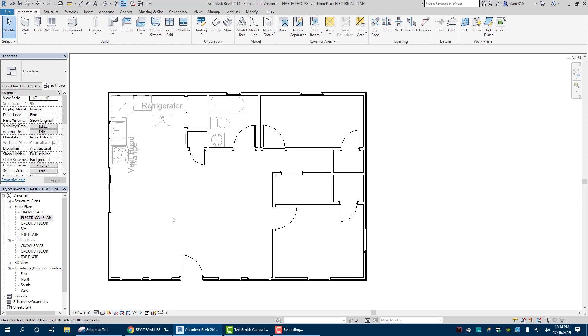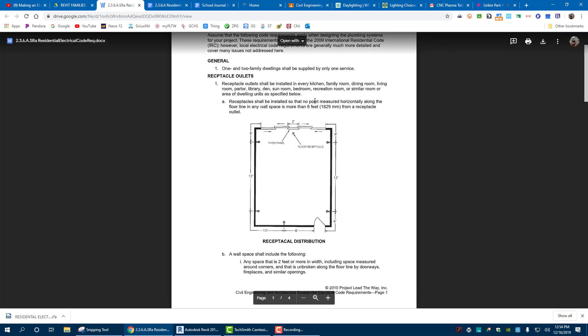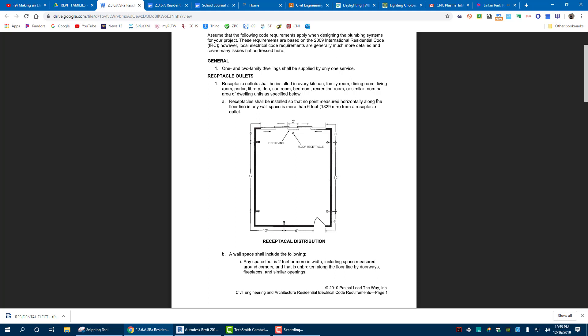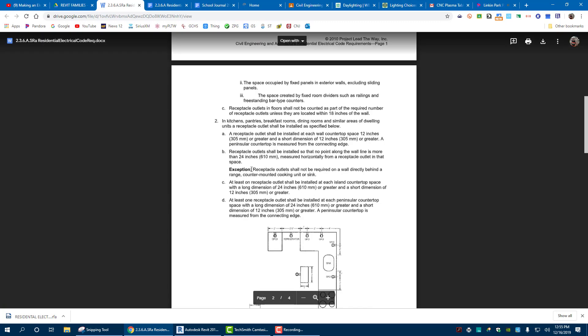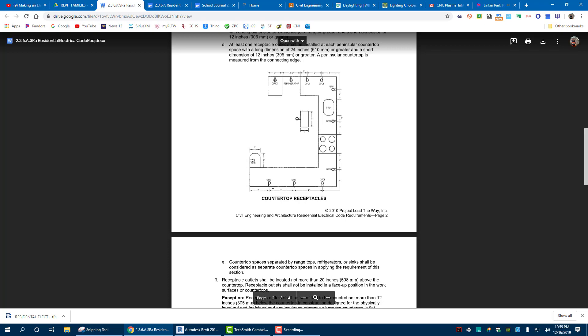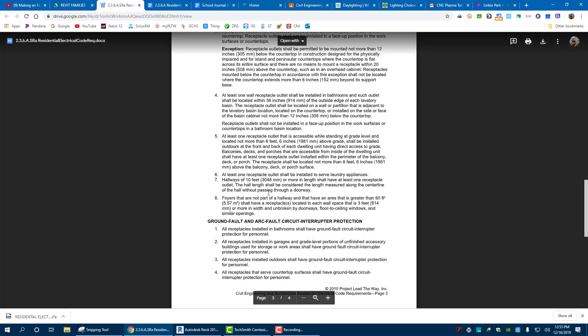Now we have the beginning of our electrical plan. We're going to begin placing outlets. Outlets and switches are all going to be placed according to our residential building codes and electrical codes. You'll need to look at these — for example, a receptacle shall be installed so that no point measured horizontally along any wall space is more than six feet from an outlet. You'll also need to figure out where to put GFCIs. I'll cover the basics of placement, but it's up to you to follow the rules.